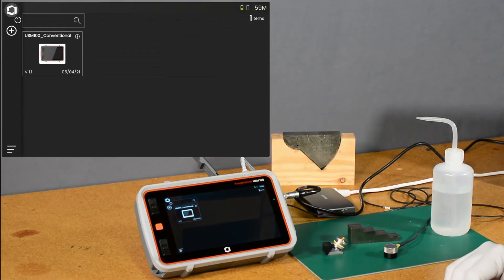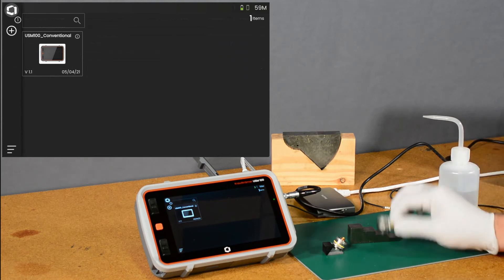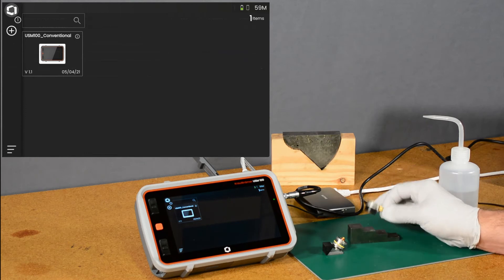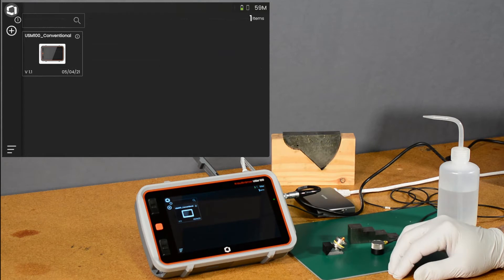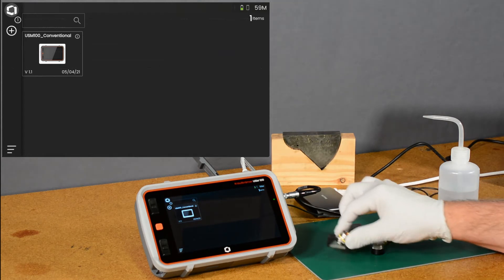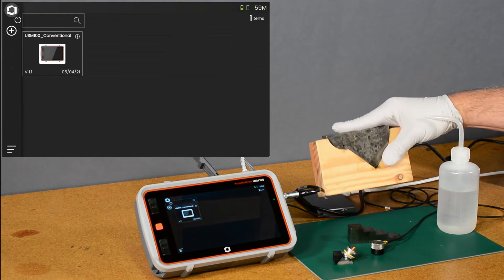We're going to look at two different ways of doing this. In the first, we're going to look at using a straight beam probe on a traditional step block, show you a quick way to get that dialed in, and then we'll look at an angle beam probe on our DSC calibration block.